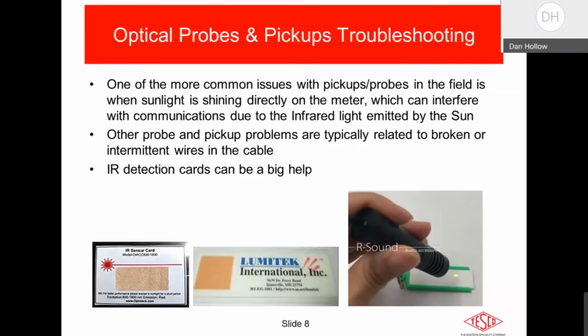We actually had a comment come in, Dan, from Jeff saying the camera on a cell phone will make the infrared visible also. Are you familiar with that? I am. I have not used my phone for that purpose before, but when I was doing the videos, I noticed that when I had a load on my meter and the optical probe was not hooked up to the meter, and I was filming the meter on that 2990 with my webcam, I could see the infrared pulses coming out of the LED on the meter. I could see the pulses. But when I turned and looked at the meter, they were invisible to the naked eye, but they are not invisible to the camera eye.